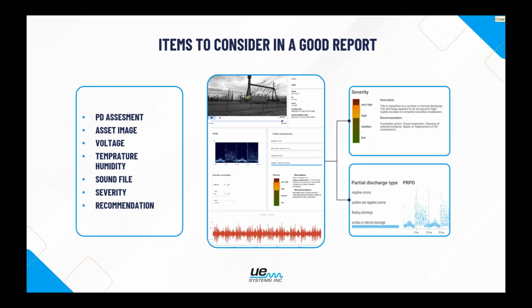So now that we know what we're looking for, as far as generating reports, there's, at least in the UE world, 2 ways we can go about it. We can either use something like the cloud-based software for a camera, or we can use something more traditional like DMS to build out a report. Regardless of which platform you decide to use, there are things to consider when building a good report. Typically, we do want to make an assessment of what that partial discharge is. Hey, based on what I'm seeing, what I'm hearing, this is corona, this is tracking. It looks like we have arcing and mechanical looseness occurring at the same time.